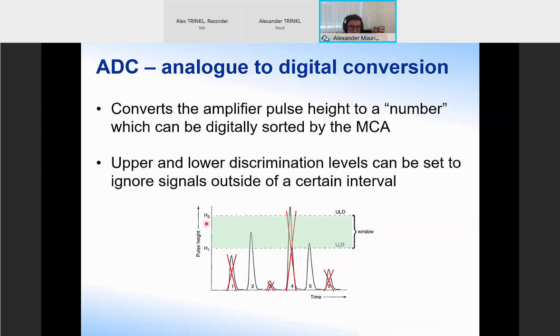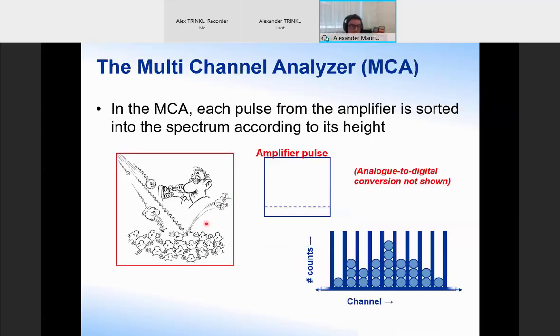Now we have some digitally converted pulse height data, and those are then sorted into a spectrum. We can imagine there's a guy sitting and counting each incoming event to our detector, like we see in the picture on the left side. That would go too slow compared to how fast the detector is working. But basically, a pulse with a large amplitude will be sorted higher up in our spectrum than a pulse with a low amplitude. Again, we're skipping here the analog to digital conversion. It's sorted into a predefined number of channels.